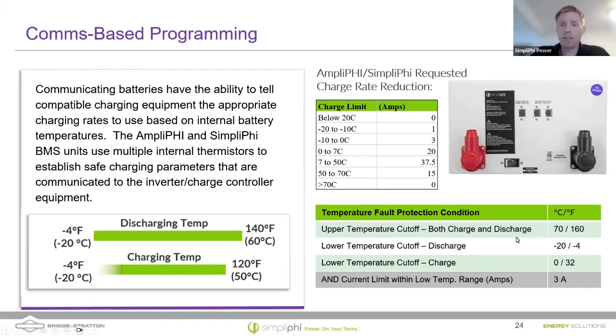If you get even colder than -20°C, the battery management system will go into a fault and protect itself. If the temperature is -40°C, I don't know if that happens normally, maybe that's a little colder than we usually get to, but I do remember in upstate New York hitting -30 Fahrenheit when I was a kid, so it can happen. The battery will open up the contactor and prevent charging and discharging until the temperature comes back into that -20°C range, and then the contactor will close and the battery will be able to operate again.